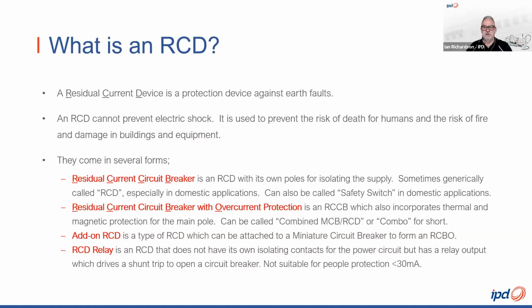RCD stands for residual current device, and it's a protection device against earth faults. We have to remember, though, that an RCD cannot prevent an electric shock. It is used to prevent the risk of death for humans and the risk of fire and damage in buildings and equipment. There's been a lot of research over the years, and this has shown that nearly 90% of electric shocks are from an active conductor down to earth. And this is exactly what an RCD can protect against.